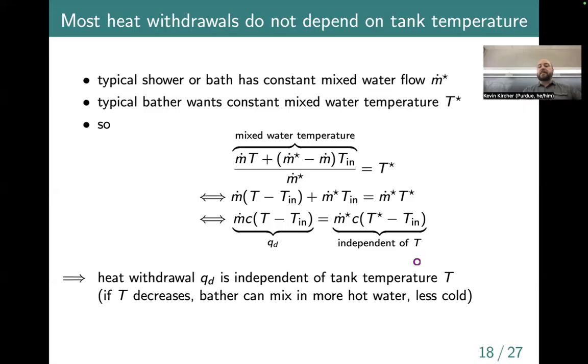So the idea is that if we store the water in the tank at a hotter temperature, people will just mix in more cold water. And so we get roughly the same energy withdrawal either way. Does that make sense?